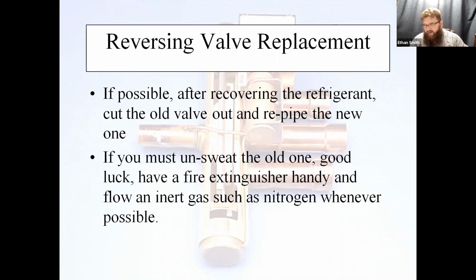If you're going to unsweat it, my advice is to have a fire extinguisher handy. And always, guys, when you're welding, flow inert gas, usually nitrogen, so that you don't have problems with your new valve as well. Regardless of whether you're going to unsweat it or not, you've got to flow nitrogen both when you're unsweating and when you're welding in.